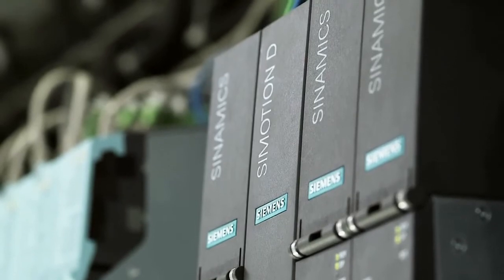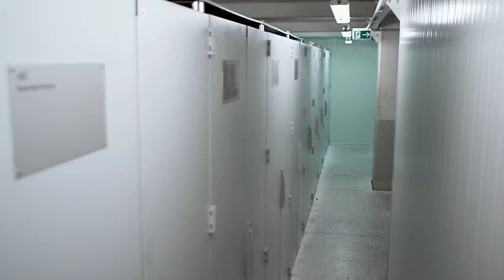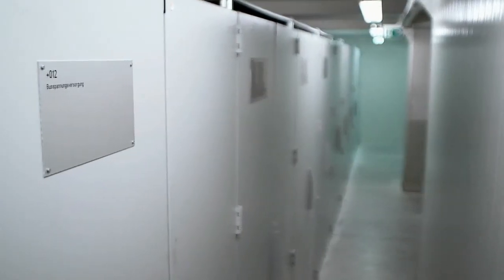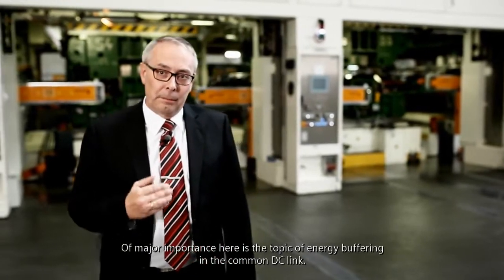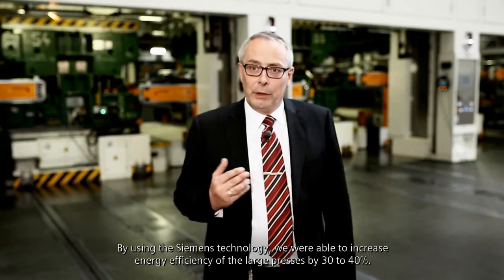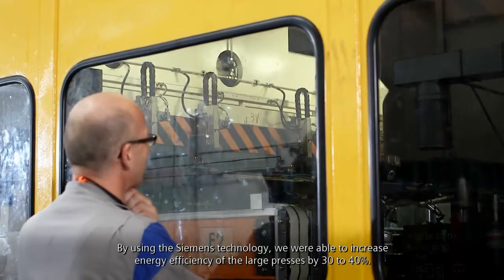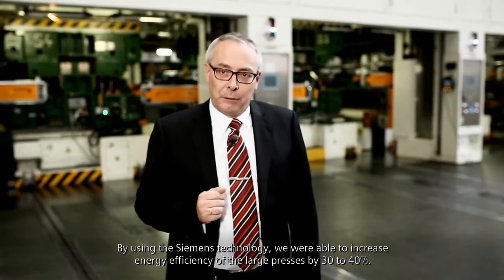Another special feature is energy management. The main and transfer drives are coupled in a common DC-link, which allows a direct exchange of energy. There is mainly the issue of energy buffering in between. Through the use of Siemens technology, we have managed to increase the energy efficiency of the large presses by 30–40%.